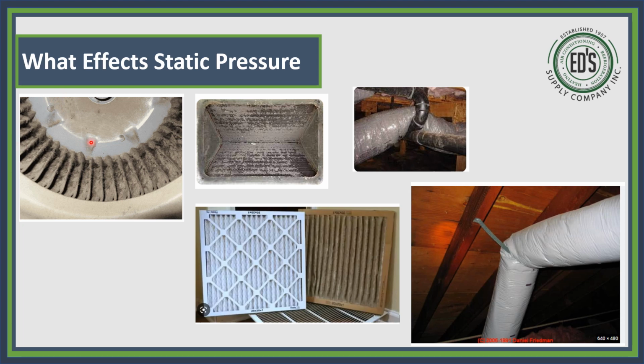Here are other things that will affect static pressure. I've been in houses and seen this, where this is an older system. Make sure you have those off, because all they're going to do is paddle the air instead of scoop and throw the air. This is a huge issue with static pressure. There's blockage, so that's going to cause resistance. Or flex going under a house over water pipes, smashed up against the floor here. You've pinched that down to a third of its size.